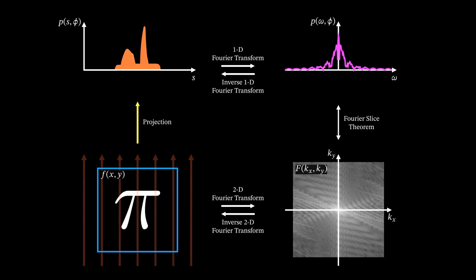In order to make the reconstruction, we have to go to the frequency domain by applying a 1D Fourier transform. And then we apply the Fourier slice theorem, which states the following. A one-dimensional transform of the projection function at the angle phi is exactly the same as the line at angle phi through the two-dimensional Fourier representation of the entire object. With an inverse 2D transform, we can then come back to the original image.